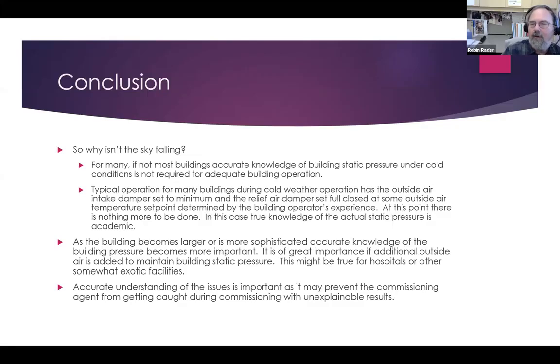Now, as the building becomes larger or more sophisticated, accurate knowledge of building pressure becomes more important. It's of great importance if additional outside air is added to maintain building static pressure. This might be true in hospitals or other exotic facilities. Now, as far as a commissioning agent goes, accurate understanding of these issues is important to prevent you from being caught up during the commissioning with unexplainable results. So you need to know the effect of cold air on building static pressure sensing tubing, and if it's causing you trouble, you need to address it. So that is my talk, and I will answer any questions.